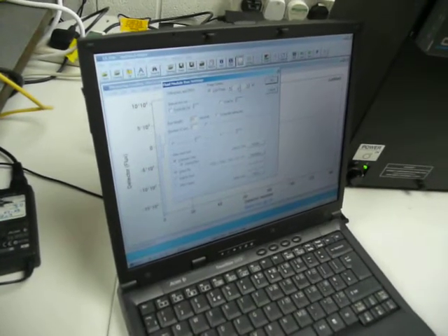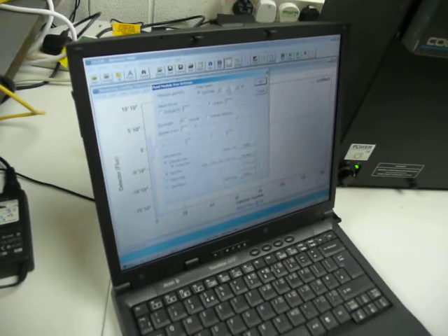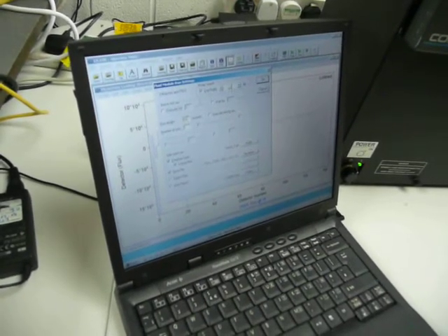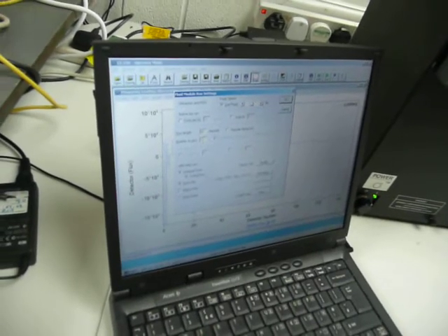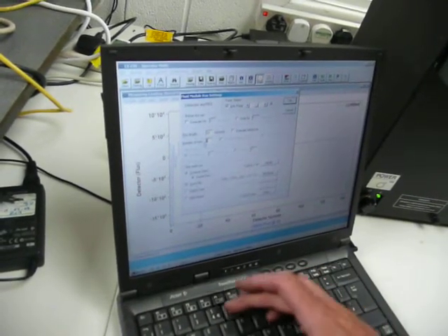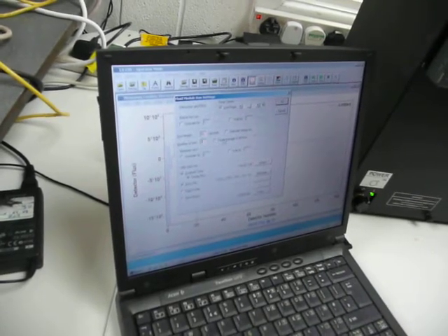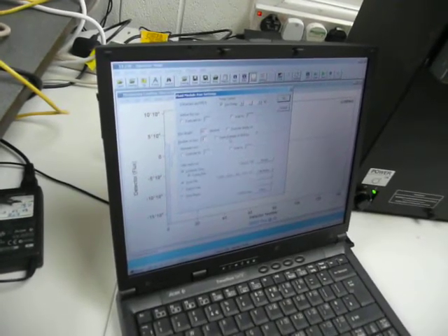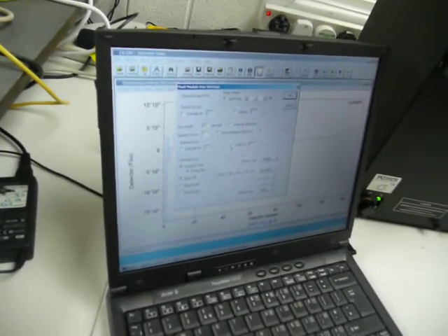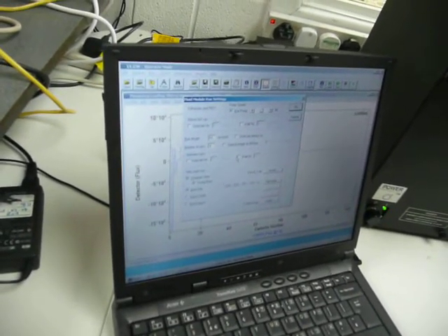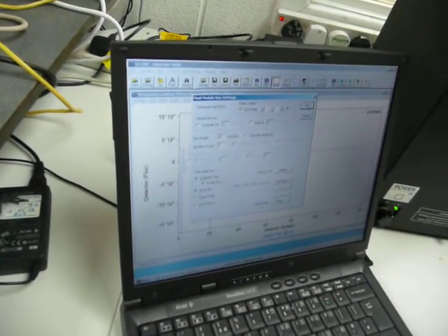That brings you on to the run settings, where you can adjust the speed of the pump to make sure that all of the particles are kept in suspension and pass through the sensing area. How long you want it to run for, how many runs you want to make. Some people like to make, for example, 3 runs. If I put in 3, then I get the opportunity of averaging all 3 runs. I can wait for seconds between runs, so if we're looking at changing systems, we can do that. You can pop that back to 1.